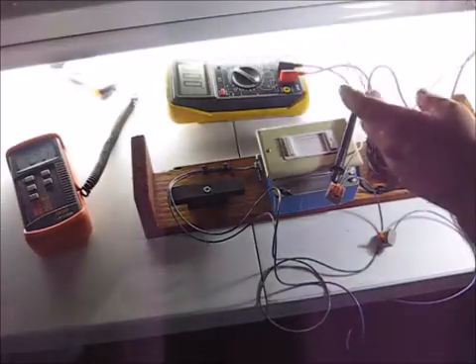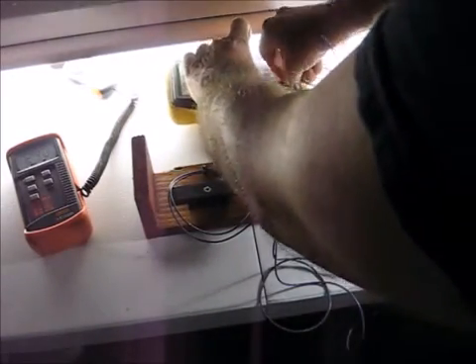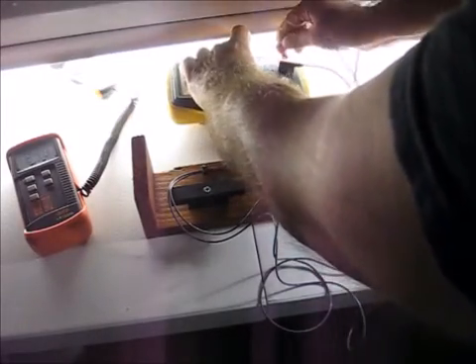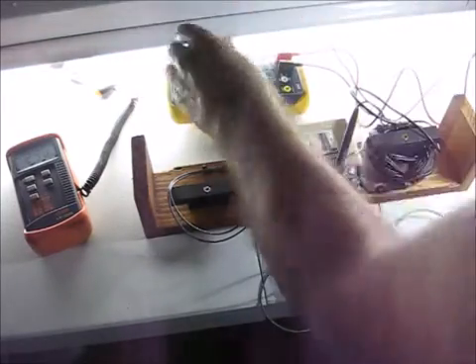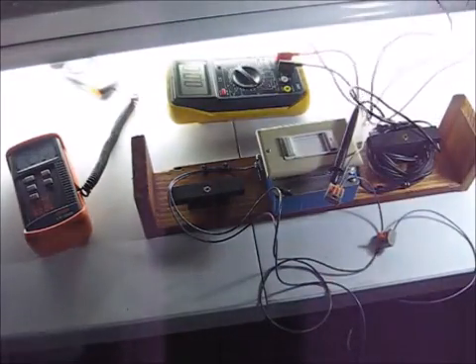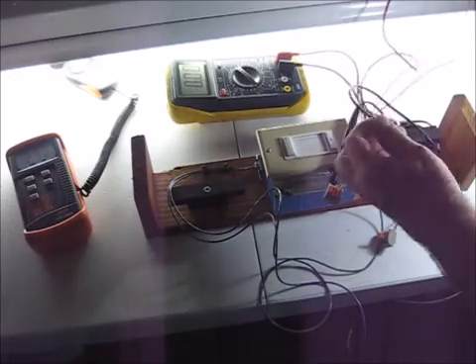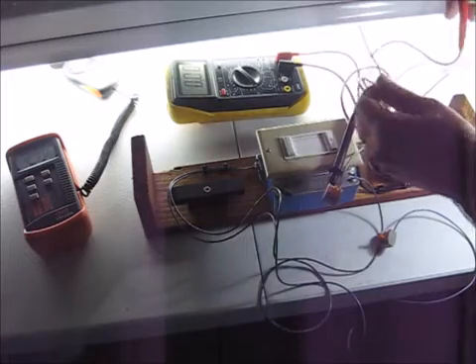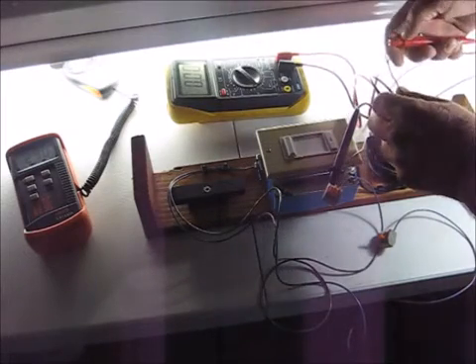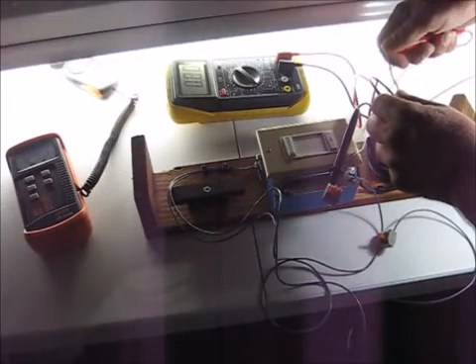I'm just shy of 200 microamps. And so that is telling me that if I stack five of these 0 to 10 volt ballasts in a space and parallel their current leads, the gray and the violet, I'm going to be seeing about 1 milliamp. So you need to see what your control is capable of sinking.